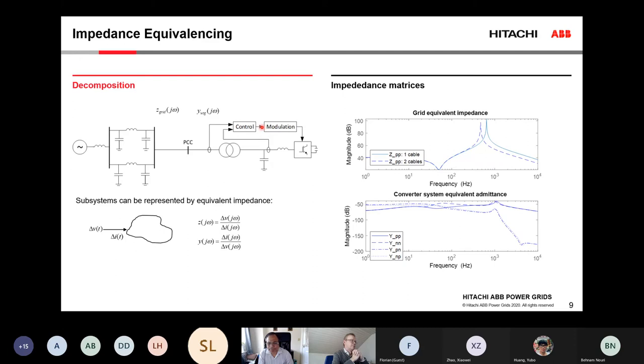Right. If there is no hands on, Matt, can I ask you a couple of doubts that I have? Yes. Right. Also, we have one activities. As you initially said, the BorWin wind farm, when that 200 megawatt could never become 400 megawatt because of these instability issues, we started working on the Alstom grid project Dolwin 3. And there we did a detailed modeling, and there it's all series of projects. And we found that it was more of the resonance instability than of harmonics, because also in your slide, you showed something as 290 hertz, which is not coming as any multiple of 50 or 60.